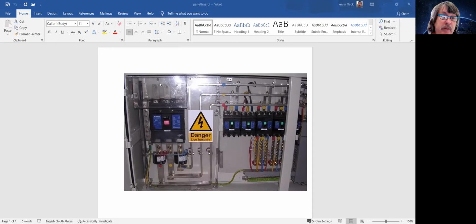And we can see here that without that interface barrier, there is a risk of a short circuit occurring after a large short circuit trip on the breaker itself. So ionized gases come out the top of these particular products. And if you don't have those barriers fitted, you will end up with a secondary calamity between the phases, which will result in a short circuit external to the breaker, resulting in a lot of damage.